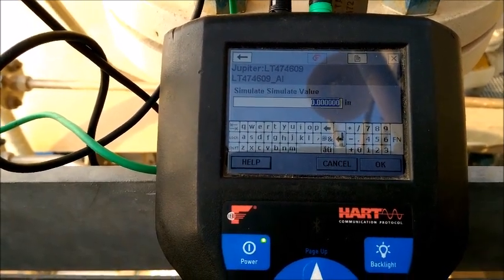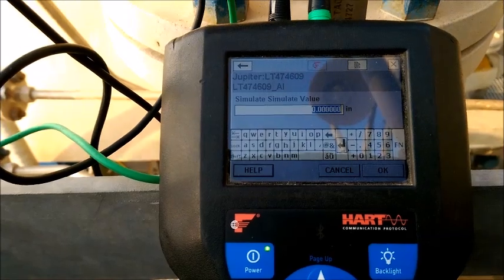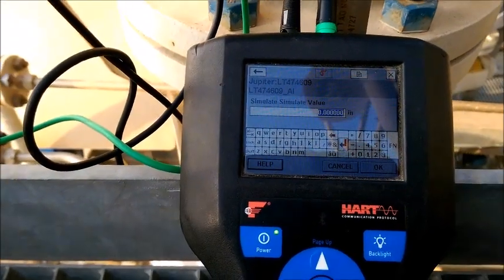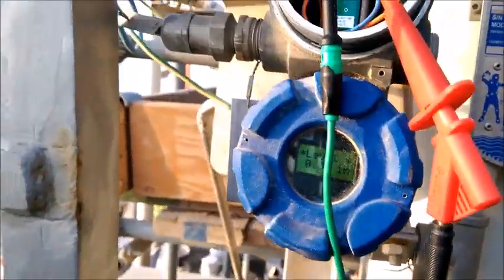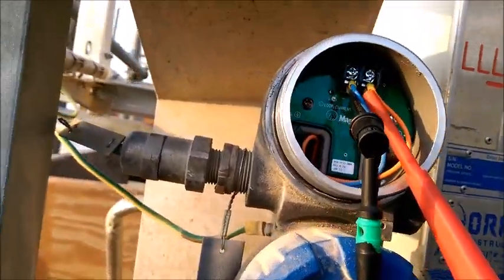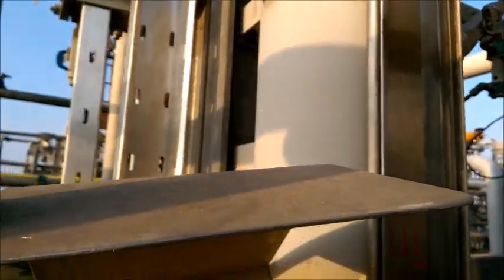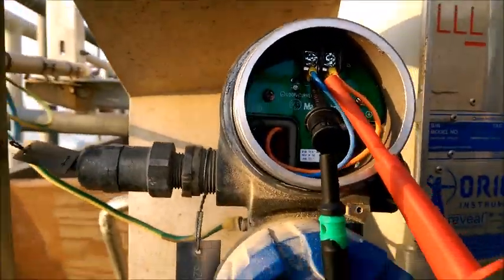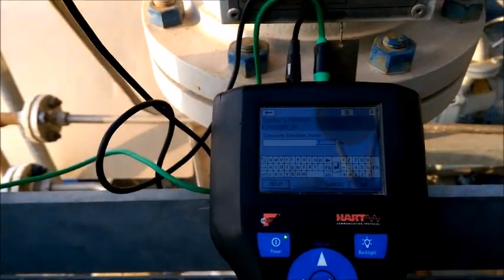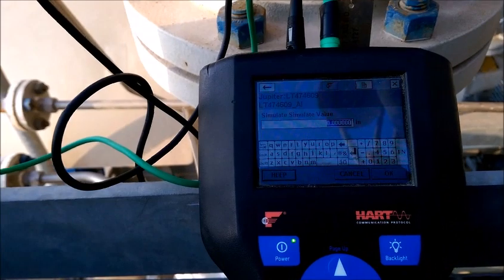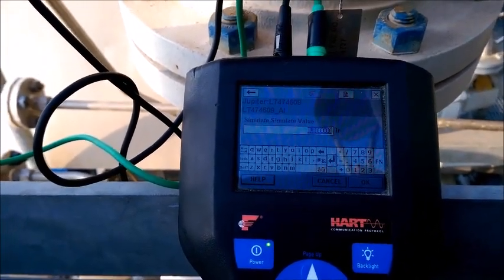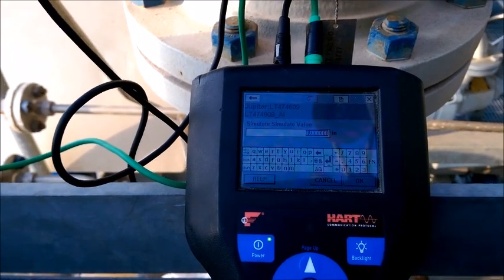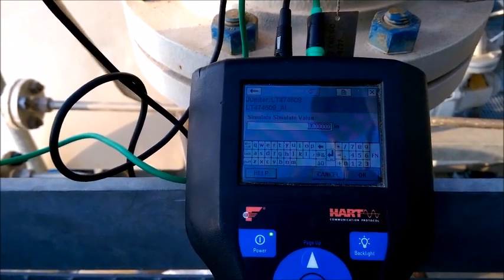The simulate value is showing in inches. We should apply the value in inches because in this transmitter there is a level gauge inside. This length is 15 inches, so it is 0 to 15 inches mapped as 0 to 100 percent. I applied the value — already 0 percent is showing as 0 inches, which is 0 percent.